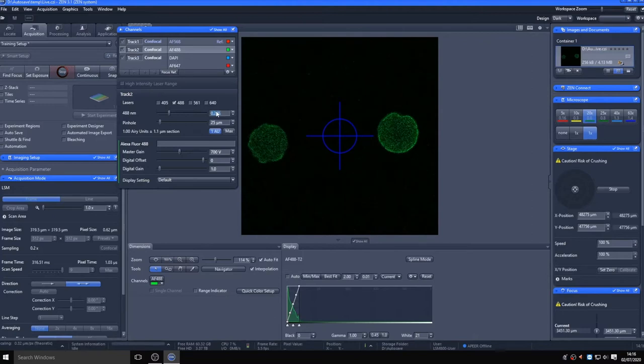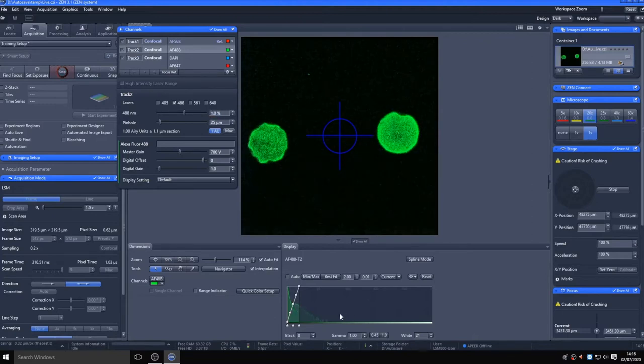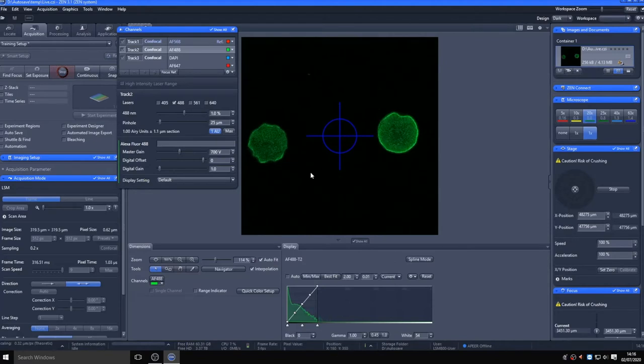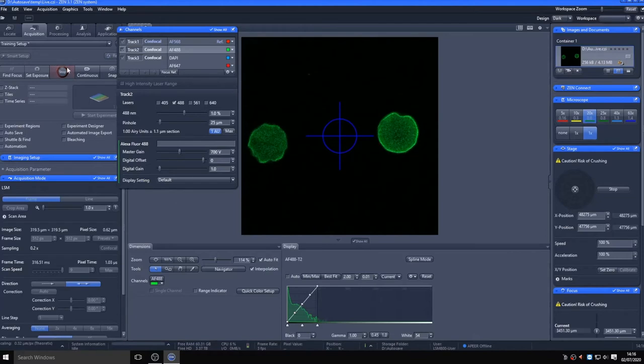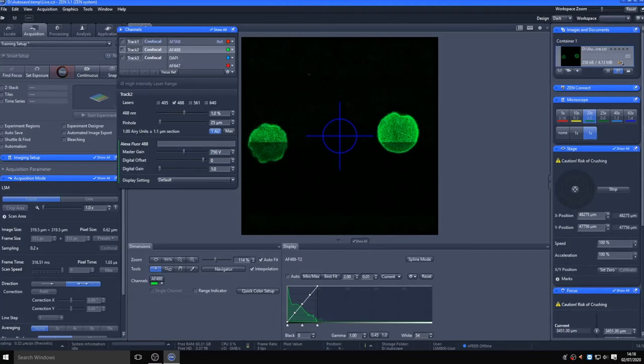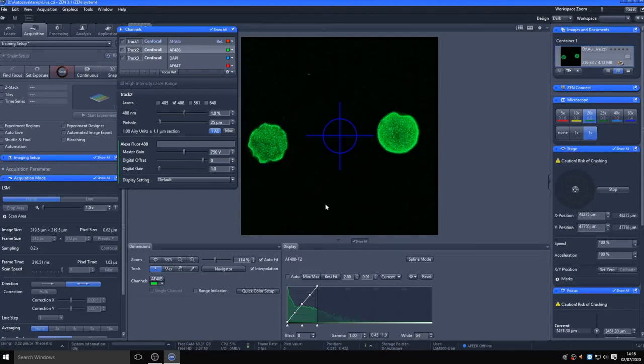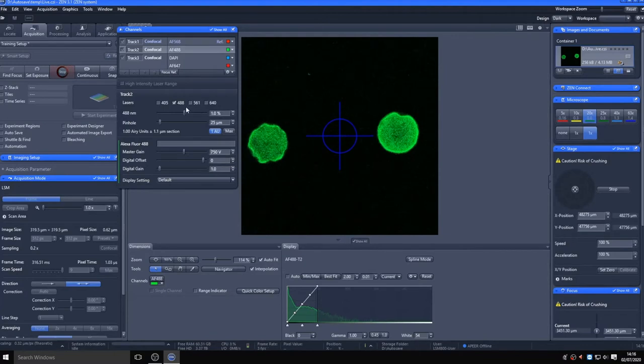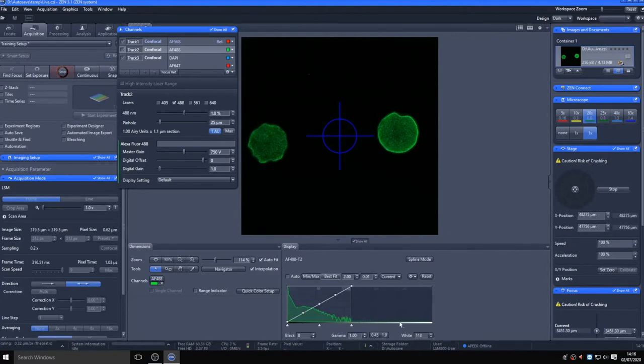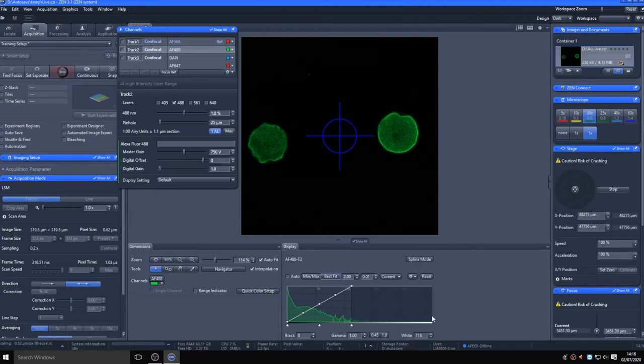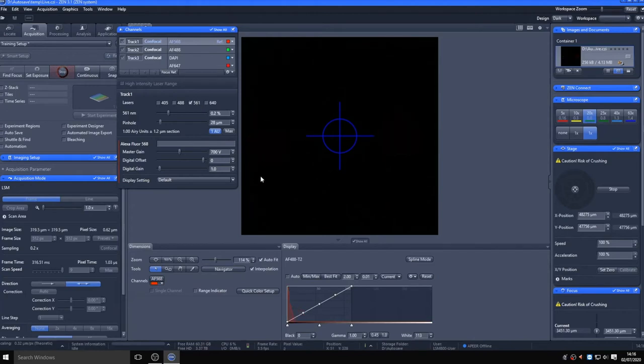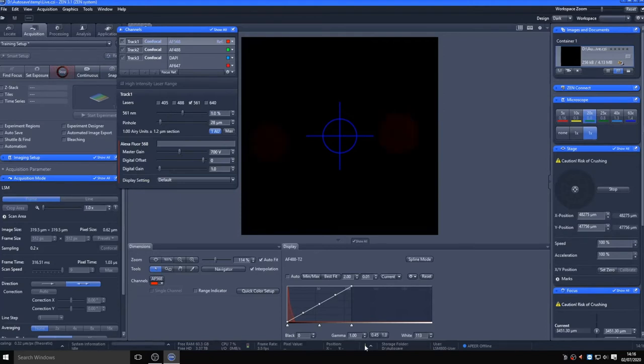With that said, we can go live again and set the laser power and gain for each of the channels in turn, using the histogram as a guide and increasing the amount of signal to increase the dynamic range of the data captured, whilst avoiding overexposing any regions of the image. You will notice that moving through focus will also affect the intensity, so ensure you are in the brightest focal plane for setting laser and gain, especially if you are aiming to do Z-stacks. Ensuring I don't fill the histogram means that I also have dynamic range to play with in case regions of the sample are brighter. Repeat this for each track, adjusting laser and gain to suit your final image.